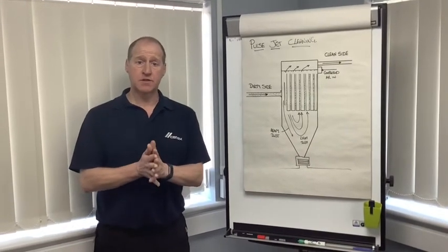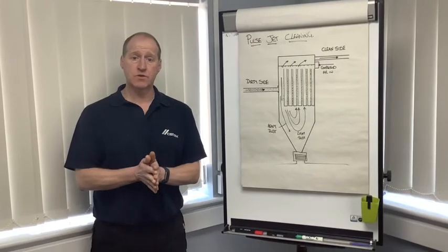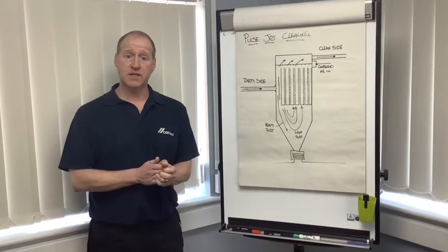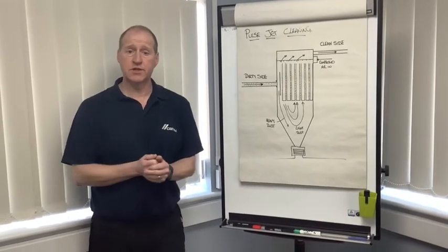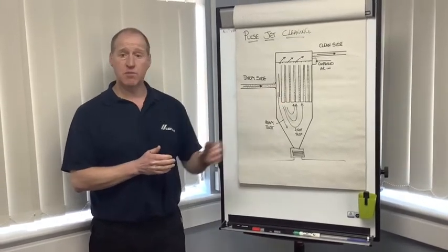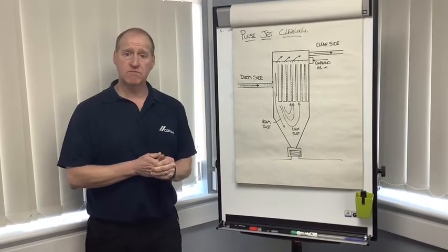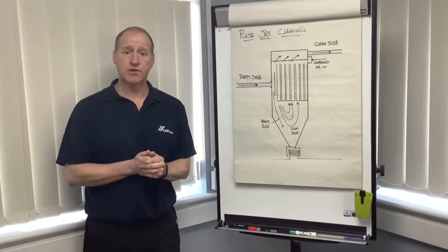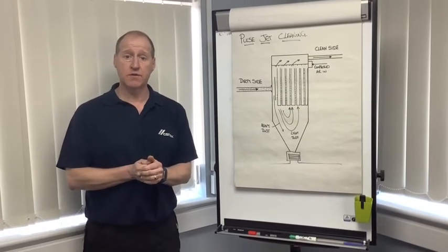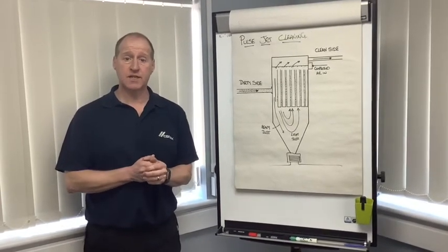Schedule in for your maintenance costs every 12 to 18 months to replace this rotary valve. Because when we do have a stack test, £660, and we have a failure, typically you would have to change the bags, change the valve, everything comes to a category A. It's a failure. We need to be ethically minded about what we do to prevent all stack test failures.